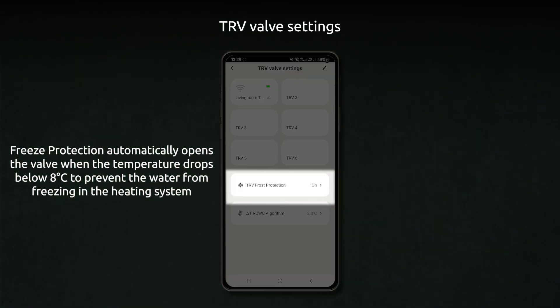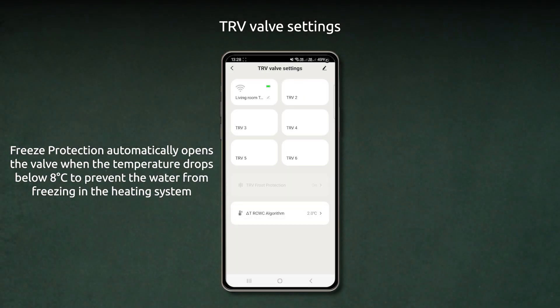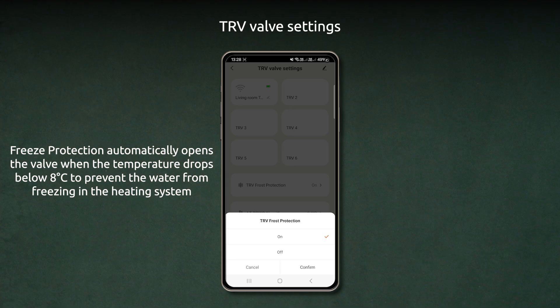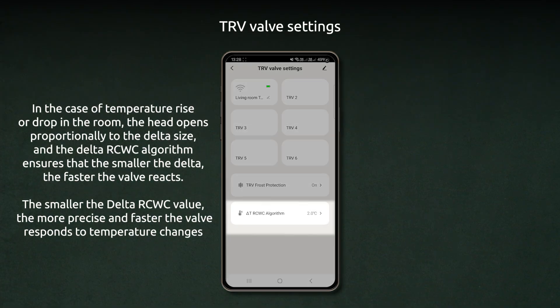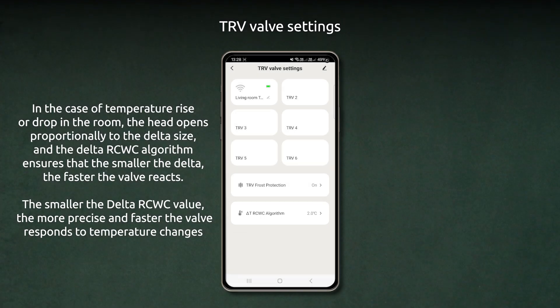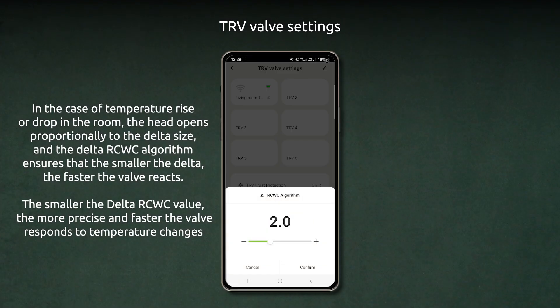Freeze protection automatically opens the valve when the temperature drops below 8 degrees Celsius to prevent the water from freezing in the heating system. In the case of temperature rise or drop in the room, the head opens proportionally to the delta size. The delta RCWC algorithm ensures that the smaller the delta, the faster the valve reacts. The smaller the delta RCWC value, the more precise and faster the valve responds to temperature changes.